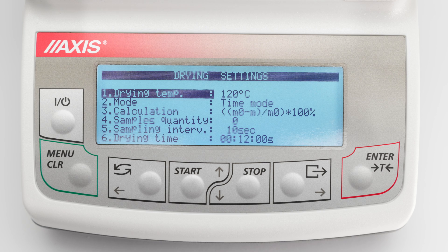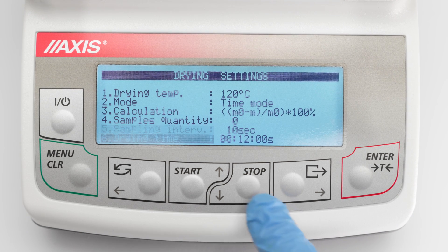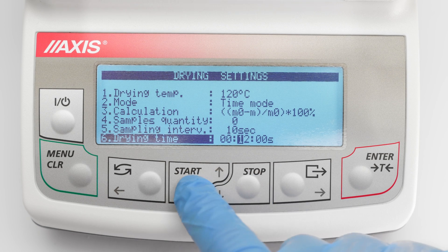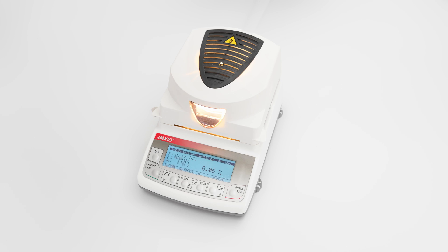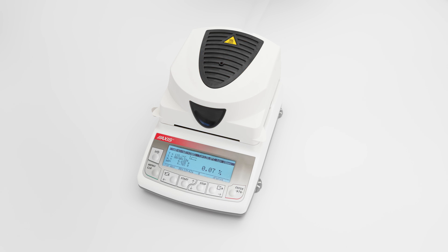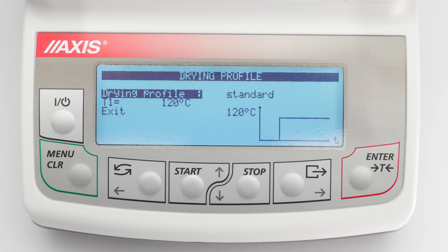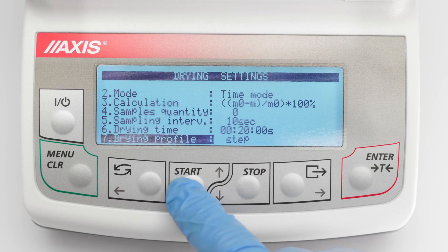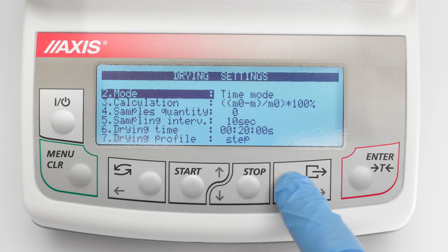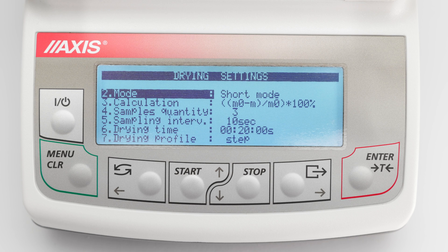Proper adjusting of drying time also needs user attention. The minimum drying time is the one after which the sample will no longer change its mass by more than the measurement error allowed by the user. After carrying out several measurements with the designated drying parameters and making sure that repeatability of the results is satisfactory, you can start optimizing the measurement time by selecting a more favorable drying time. For some materials that lose moisture very slowly, remaining in time mode may be more beneficial.